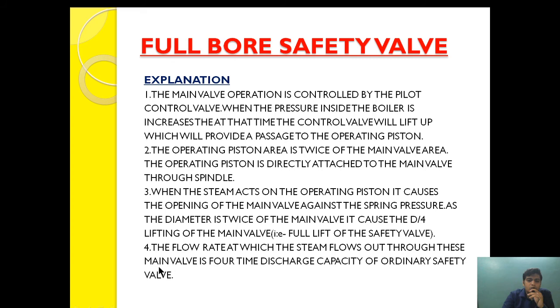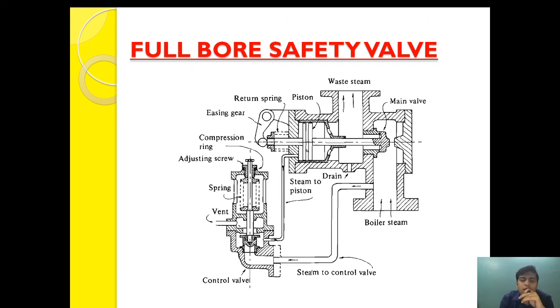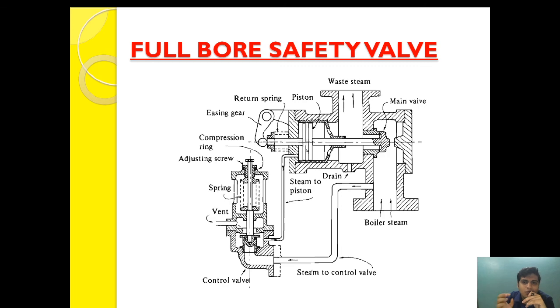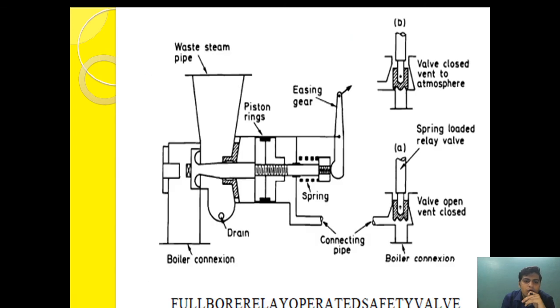The flow rate at which steam flows out through the main valve is four times the discharge capacity of the ordinary safety valve — a very important point. The lift achieved is D/4, compared to D/12 in the case of the improved value safety valve. The discharge capacity of the full bore safety valve is four times more than the ordinary safety valve. This design also shows how the control valve vents: when the control valve is open, the vent is closed; when it sits back, the vent is open. This is how the full bore safety valve works.